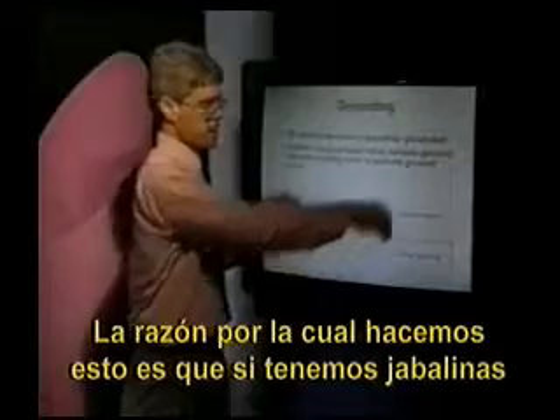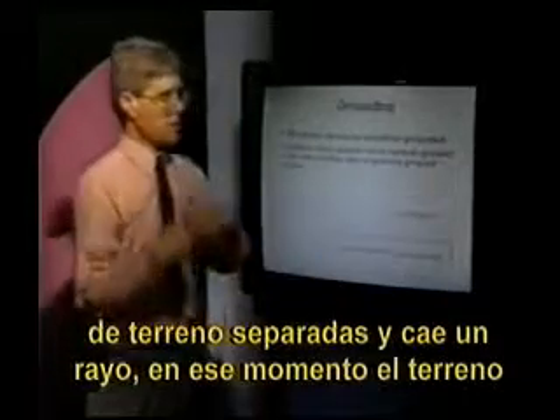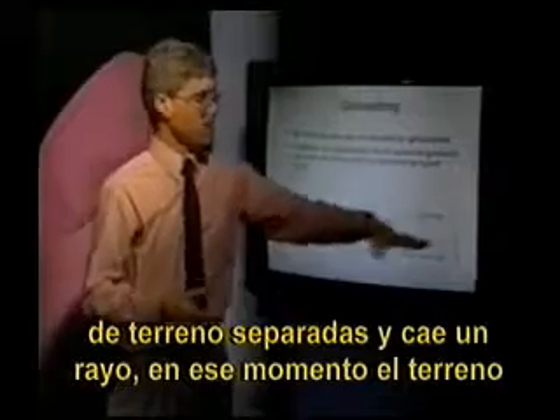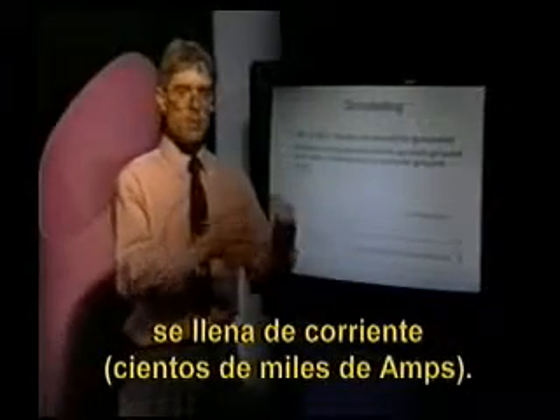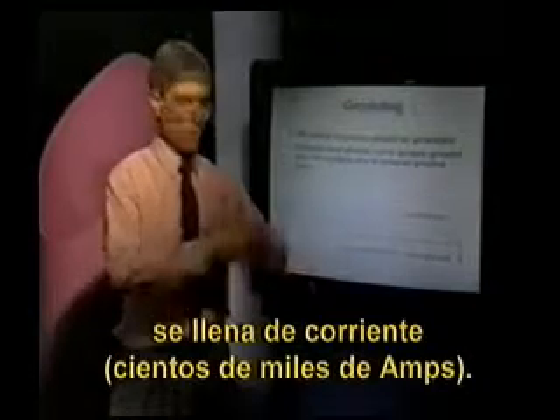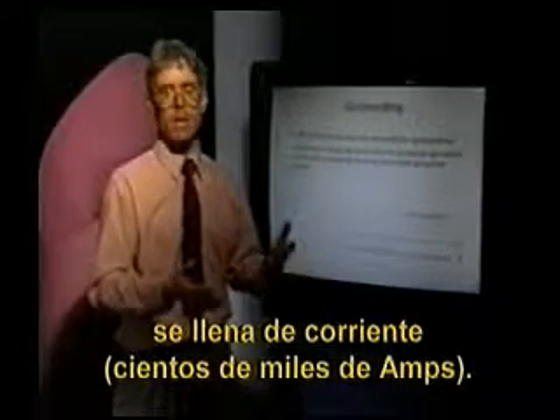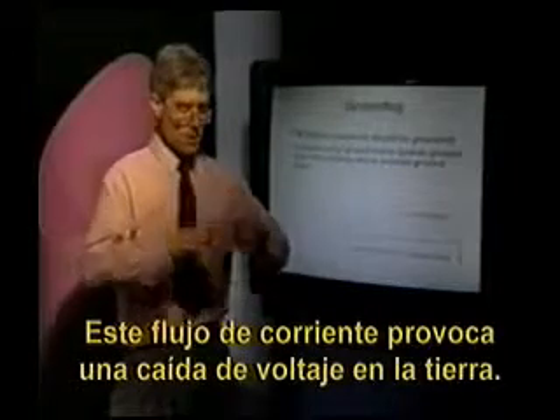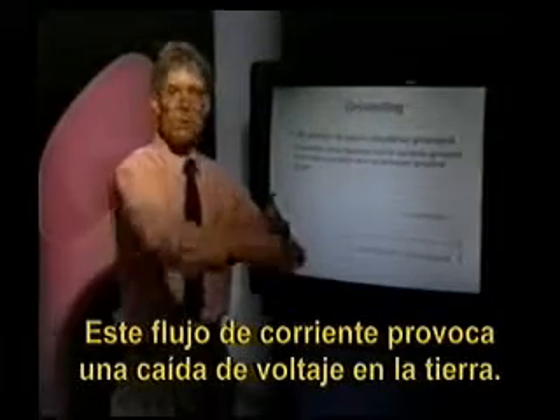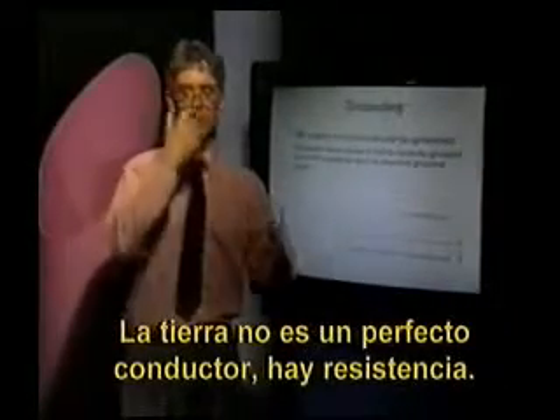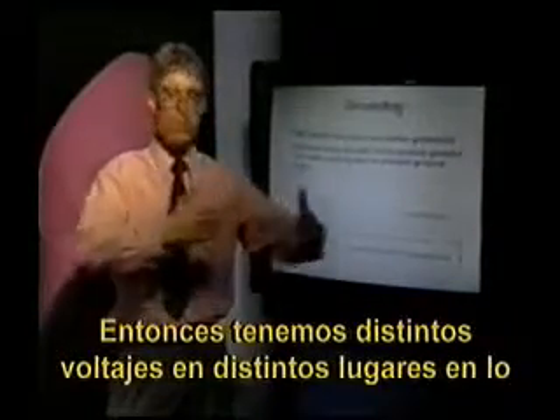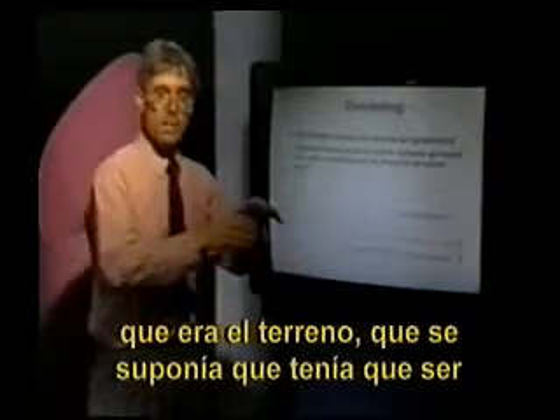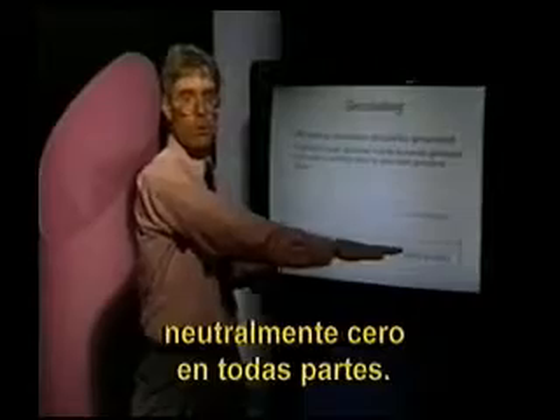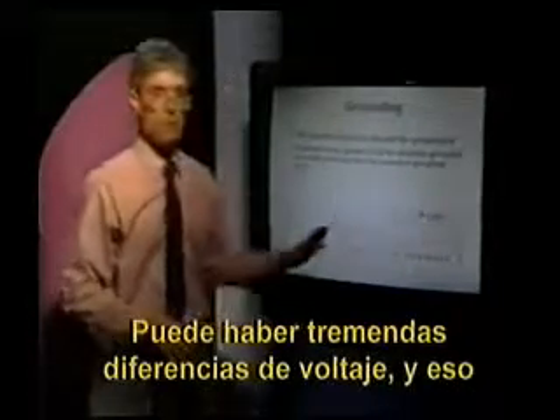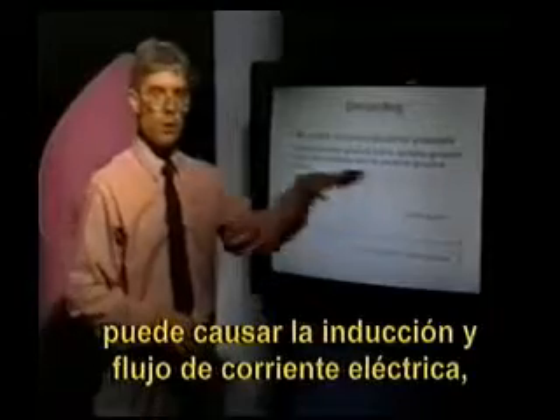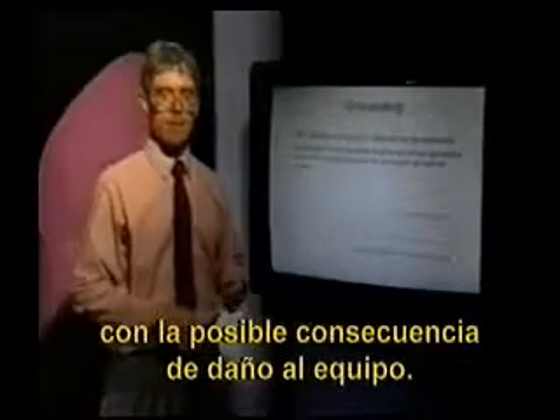The reason we want to do this is if you have separate ground rods and some sort of lightning strike, let's say, that hit the ground outside. When lightning strikes the ground, it fills the ground with current. There's a tremendous inrush of tens of thousands, if not hundreds of thousands of amps. This current flow through the earth causes a voltage drop in the earth. The earth is not a perfect conductor. There's resistance. And so we have different voltages at different places in what was the ground, what was supposed to be neutrally zero everywhere. We could have tremendous voltage differences, and this could cause electrical currents to be induced and flow and perhaps cause damage to our equipment.